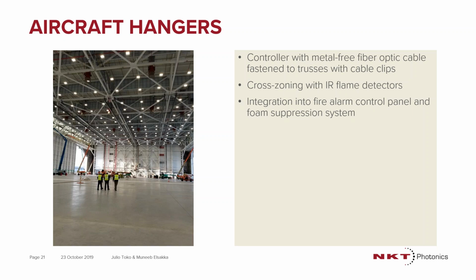When we talk about cross zoning, you could also use a traditional linear detector, but one advantage is really the fact that these airport hangars can be quite big in terms of space and area to cover, and it becomes more performance-based in the approach of how you want to do the detection system. So one example will be you can run the fiber optic linear detector on the trusses of the airport hangar and cross zone it with the IR cameras, and then you can do the virtual zoning independently. So you don't need to know exactly where the electrical cable starts or stops, because it's fiber optic, everything can be done virtually on the ground.